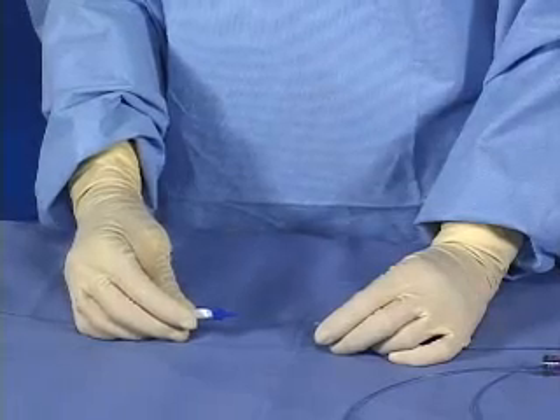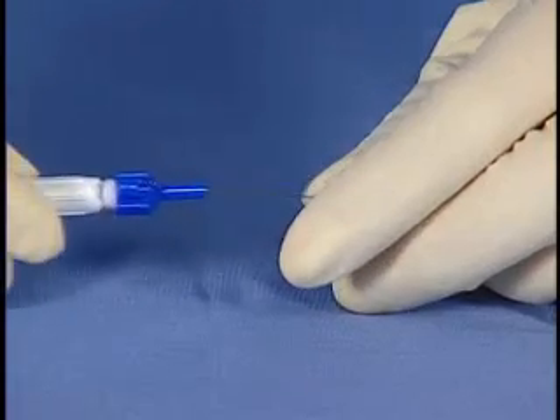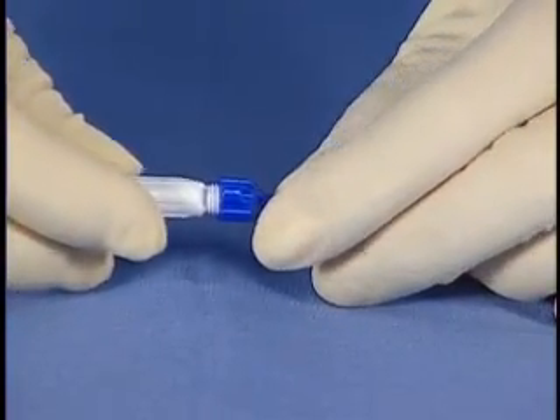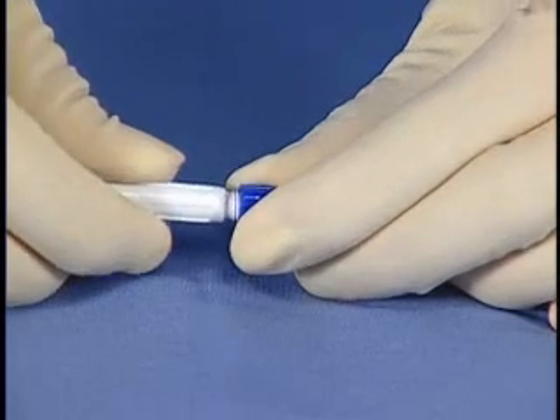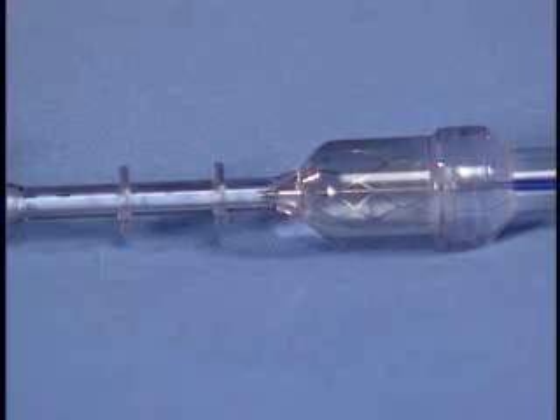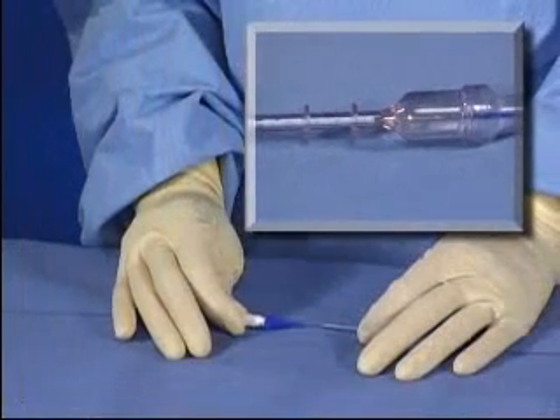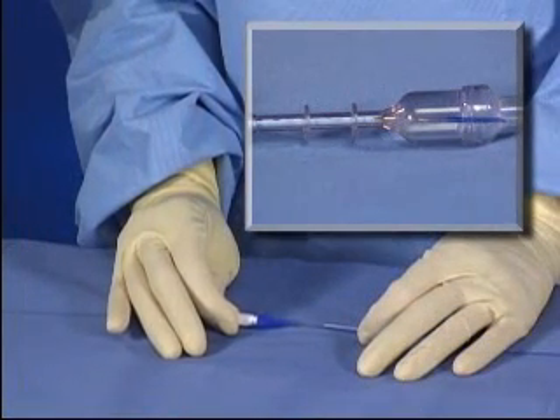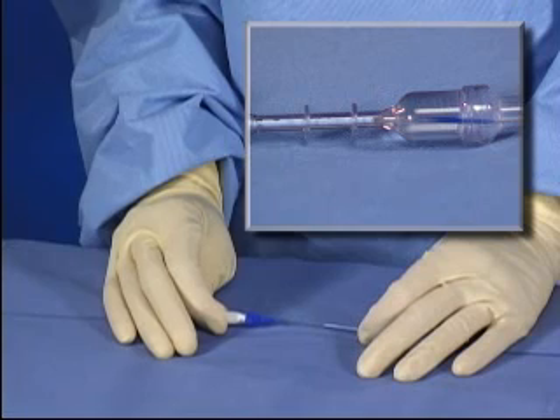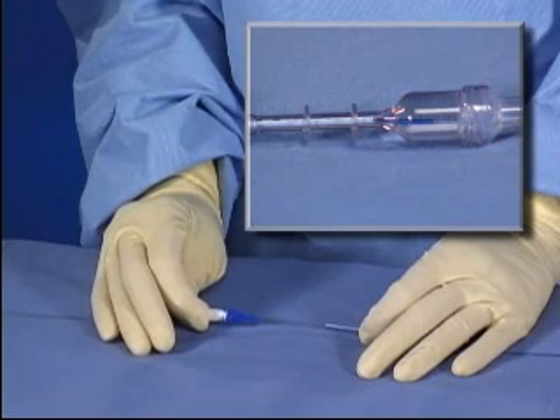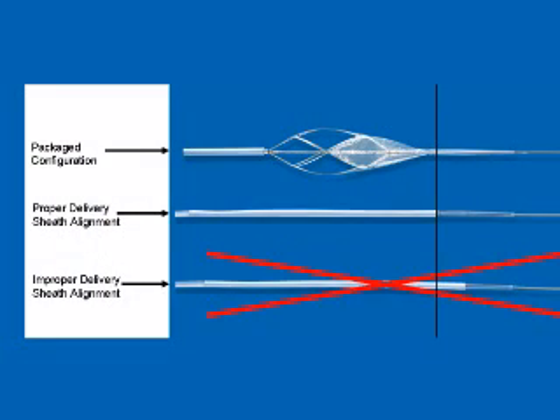Slide the included torque device with the peel-away adapter onto the wire and up to the edge of the delivery sheath. Tighten the torque device onto the wire. While observing through the flush tool, grip the delivery sheath and pull back on the torque device until the filter basket is completely within the distal end of the delivery sheath, such that the distal end of the delivery sheath is aligned with the proximal end of the dark blue filter basket obturator.